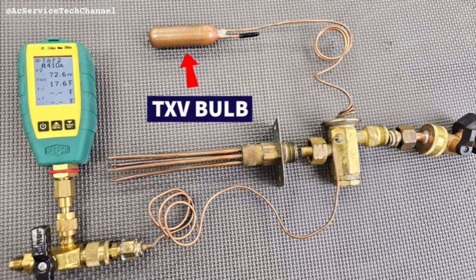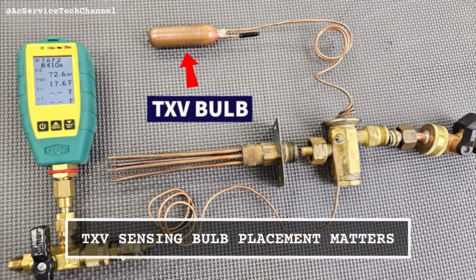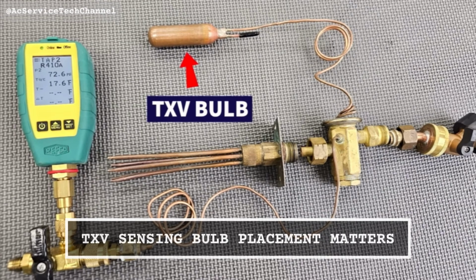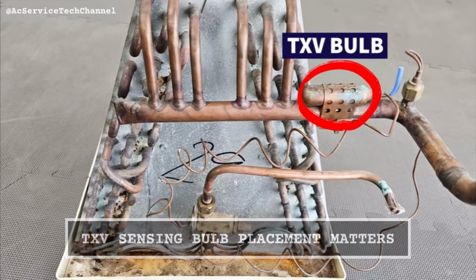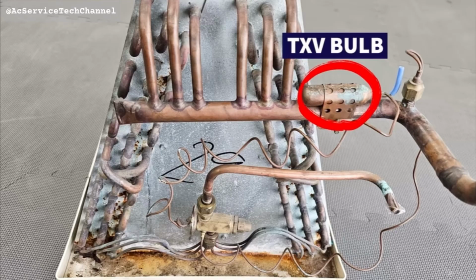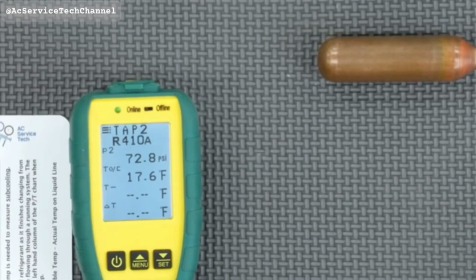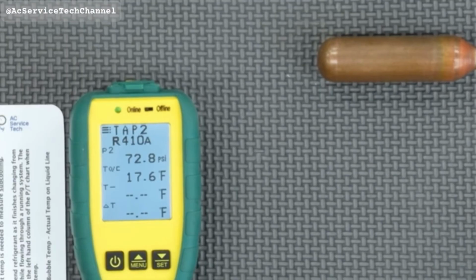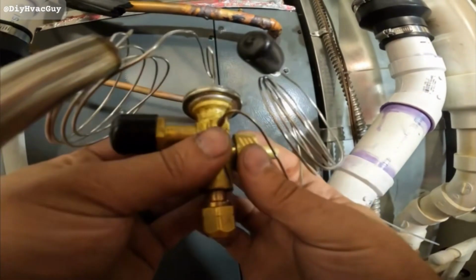Number 2. The TXV sensing bulb has to be mounted right or the whole valve lies. The sensing bulb is a small metal cylinder clamped to the suction line that tells the TXV how much refrigerant to feed. If the installer clamps it onto a bare copper line without insulating over the top, ambient air temperature corrupts the reading and the valve overfeeds or underfeeds in cycles.